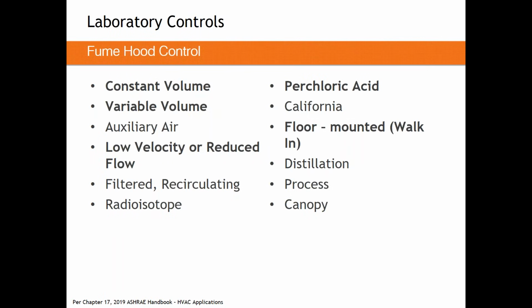But fume hoods come in a lot of different shapes and sizes, whether it's constant or variable volume, low flow, floor mounted, or perchloric. There's a lot of different types. All of these types are actually defined in the ASHRAE handbook from 2019, and that book does give a fairly good definition of each type. I want to dig into constant, variable volume and perchloric for a few seconds here.